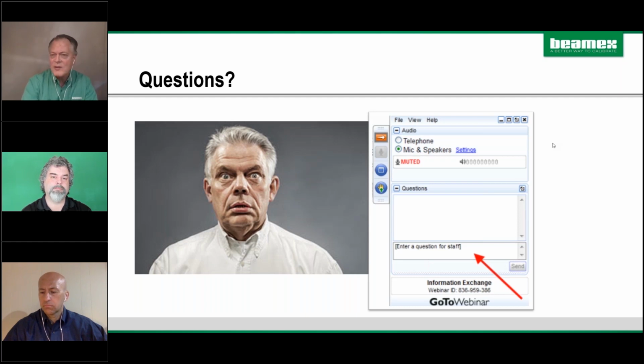What Roy just said might be your starting place. And since Beamex is into the documentation business, I say see what your sensors and technology can do, and you'll know what your tolerance is. Like you saw today, that probe is an $85 Grainger probe. It's off by half a degree, which is a pretty tight tolerance. If the tolerance was 1 degree, 2 degrees, or 5 degrees, that probe's just fine.